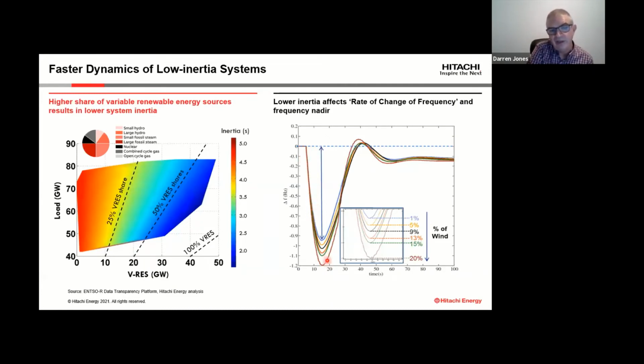This 10-second gap, when the system frequency begins to fall, is designed to make sure it doesn't continue to fall. The second salient point on this graph is called the frequency nadir, which is the lowest point that the frequency will reach in the event of a system event. So the system is designed to have enough inertia for 10 seconds to allow the secondary measures, fast frequency response and backup generation, to operate and arrest this fall in frequency, and the frequency is then brought back up. The third point on this graph is the steady state frequency, which is the point that we then need to recover the system from.